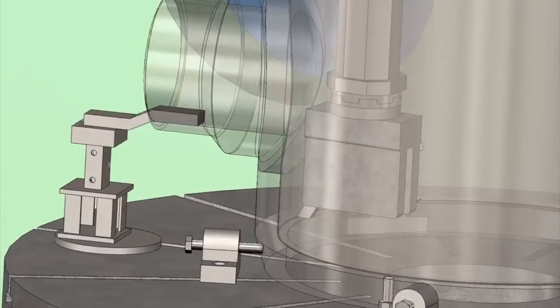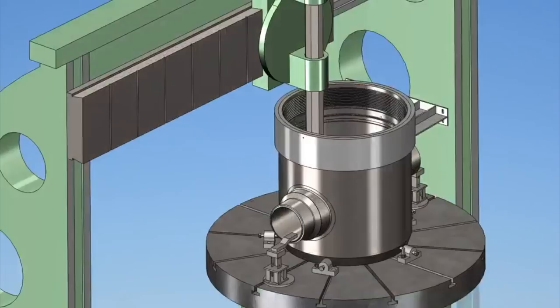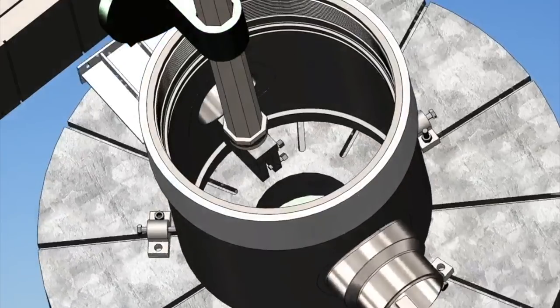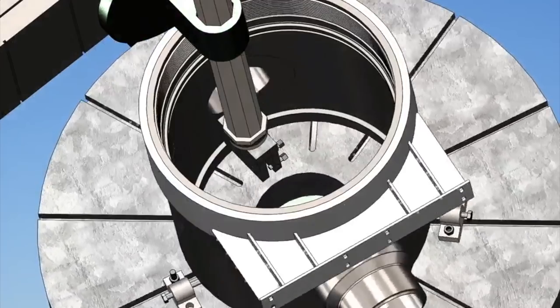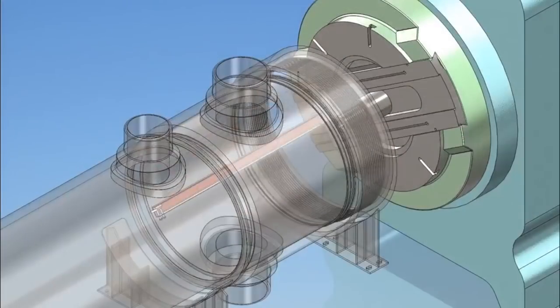We give the most importance to the channel barrel. For that reason, we take up the barrel independently on a vertical turret lathe for machining the shell to tube sheet gasket face rather than taking it up as one piece on a borer.